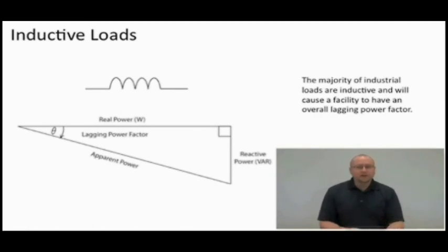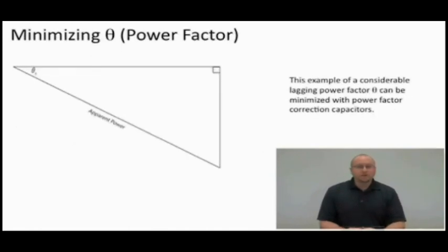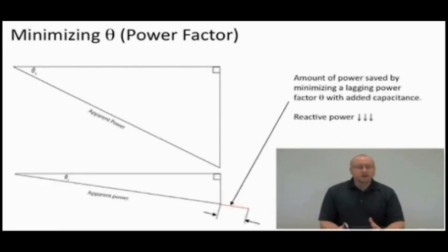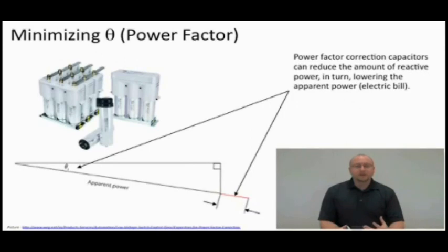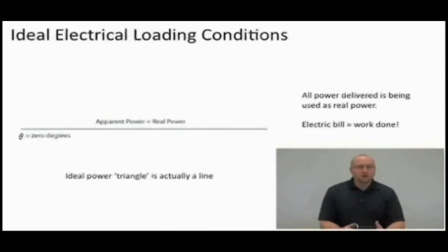Well, how can we minimize that amount of reactive power? Well, if our power triangle is going below the x-axis, like with an inductive load, what we can do is add some capacitance to it. So we have this power triangle with reactive load. If we want to minimize that and also minimize our apparent power, minimize the amount of energy that's not being utilized properly, we can add some capacitance to the system, and these are called power factor correction capacitors. You may have them in your plant. That's what they do. They minimize the phase angle difference between the voltage and the current, trying to make most of the power positive and being used by the load as real power. So that's one way that we can help out with efficiency, is minimizing our power factor on the electrical side.